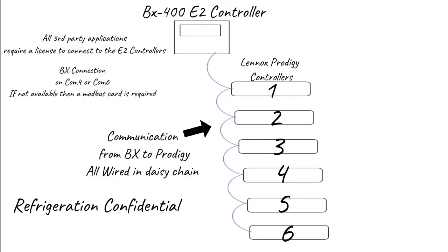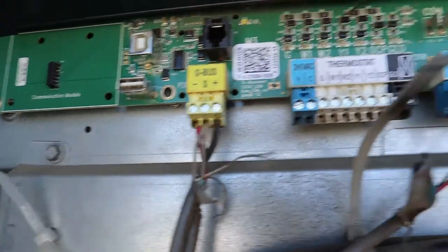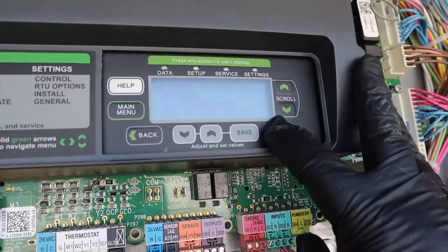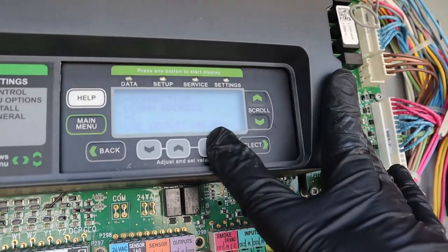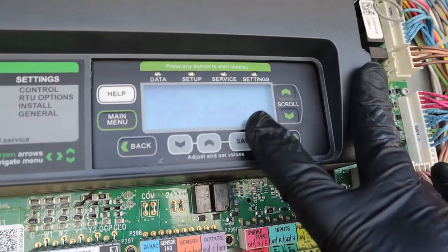Just to show you what I'll be checking — I'll be checking the addresses and wiring right here. This one has unit number one. We're checking the wiring, making sure nothing's loose or cut, and making sure it's addressed correctly. Just because it's unit number one doesn't mean it's addressed as number one, so we have to verify all the controllers.